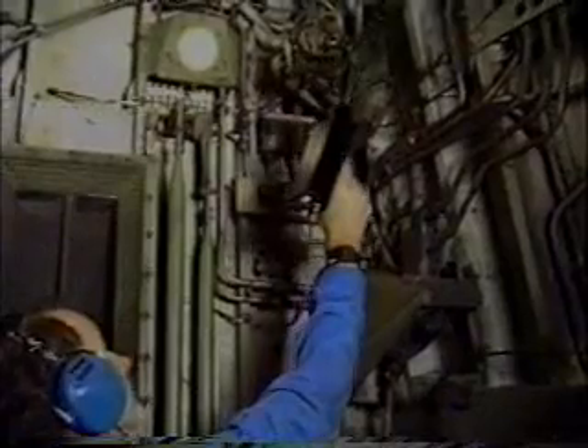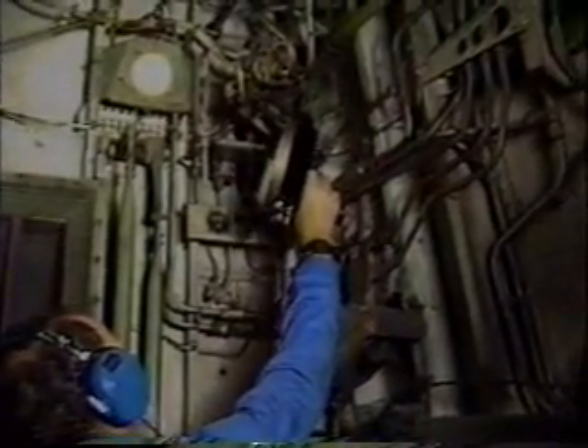For example, this is the rushing sound of a good bearing as heard through the ultraprobe's headphones. Crackling sounds indicate bearing failure. And rushing sounds, which are loud and rough, can indicate a lack of lubrication. The ultraprobe can be used in the same way as a most effective tool in all general mechanical monitoring and troubleshooting. The same method is also used to check for internal bypassing in valves and actuators of hydraulic systems.